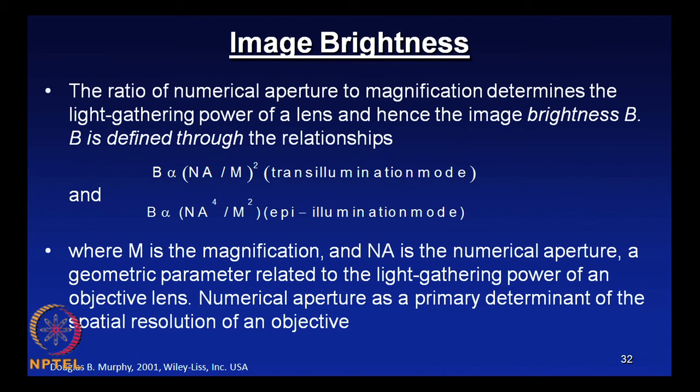Another important parameter which we talk about in light microscopy, or any microscopy, is image brightness, very important. The ratio of numerical aperture to the magnification determines the light gathering power of a lens and hence the image brightness B.